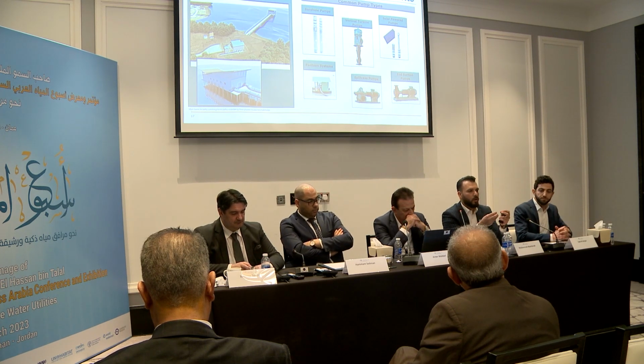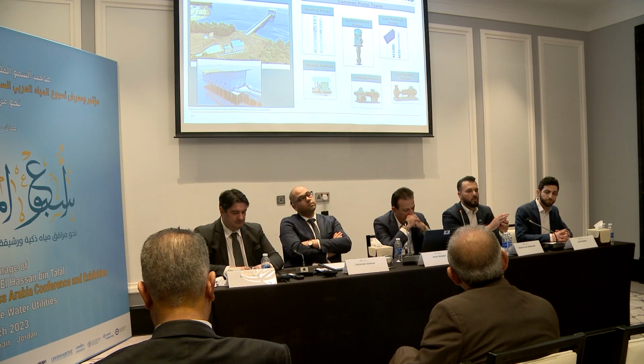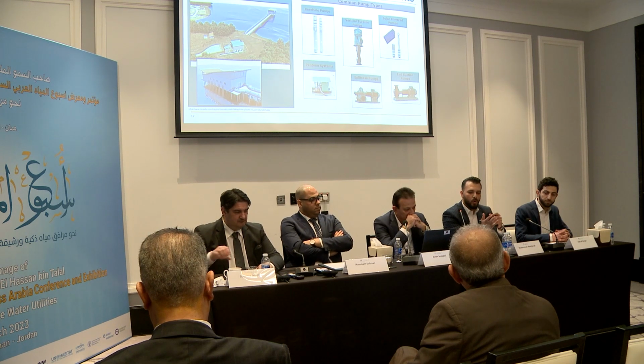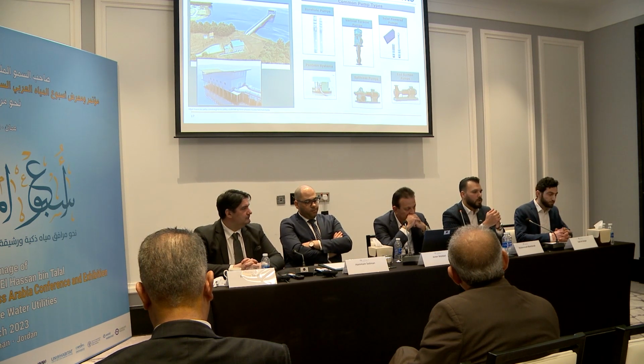For example, if you are going with a medium or jack well application, you can go for vertical turbine, deep well application, borehole pumps with submersible pump and motor, or vertical hollow shaft turbine pumps, which can go deeper, up to 100 meters and more.